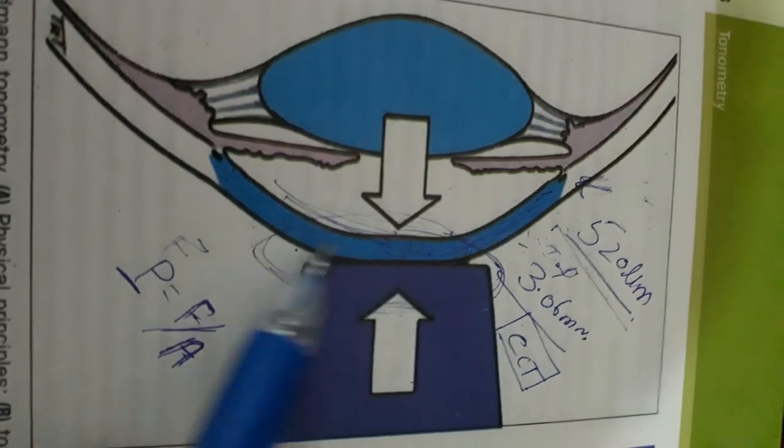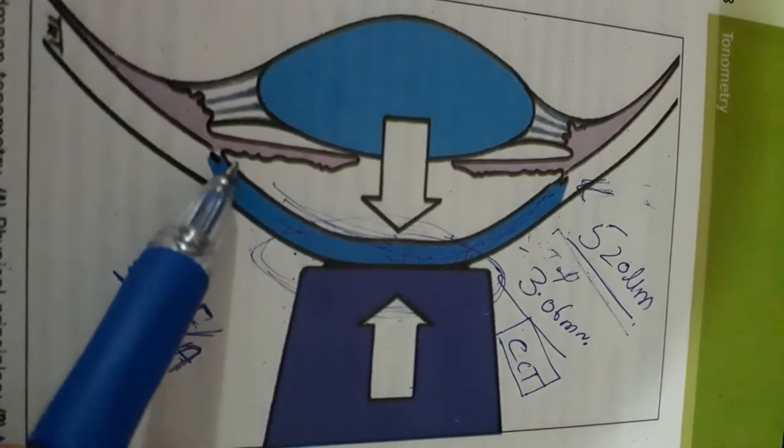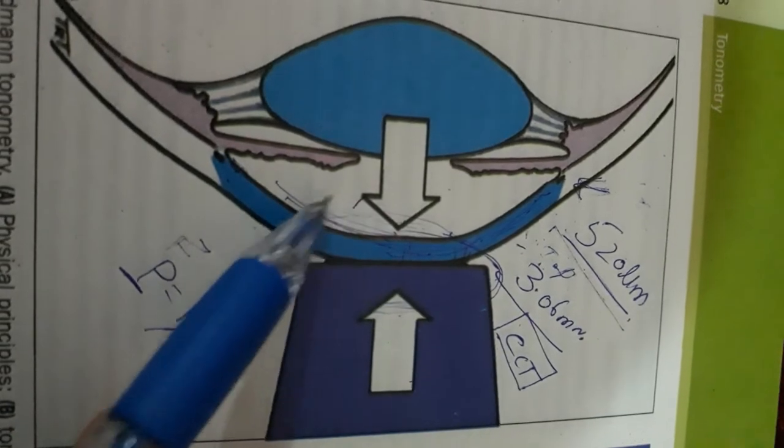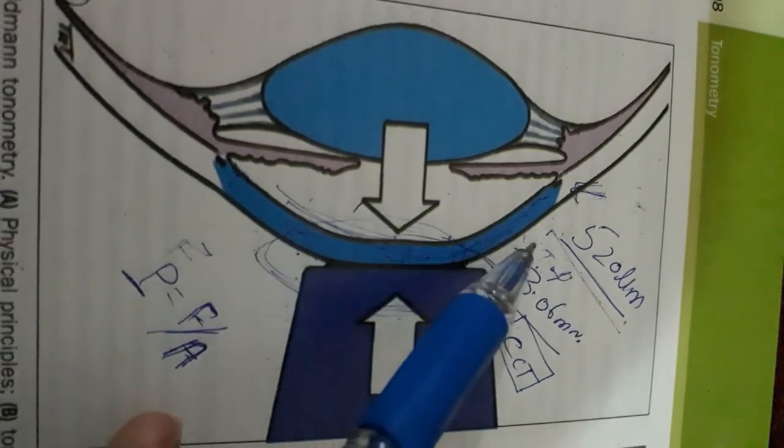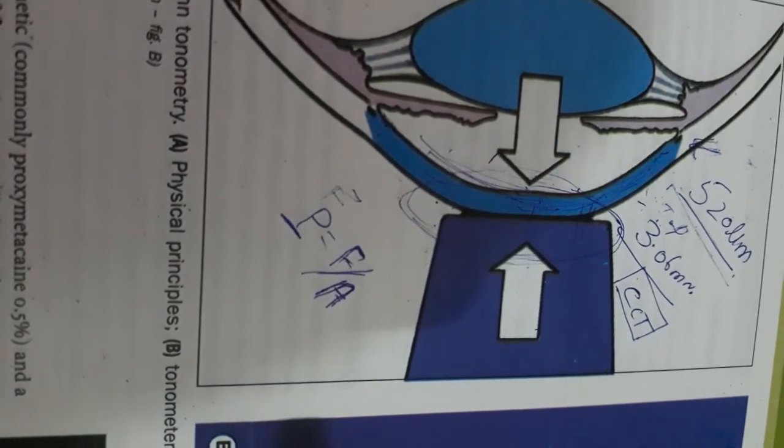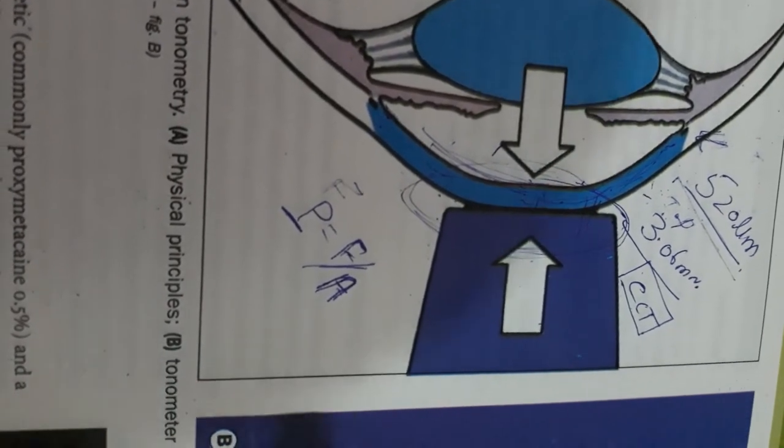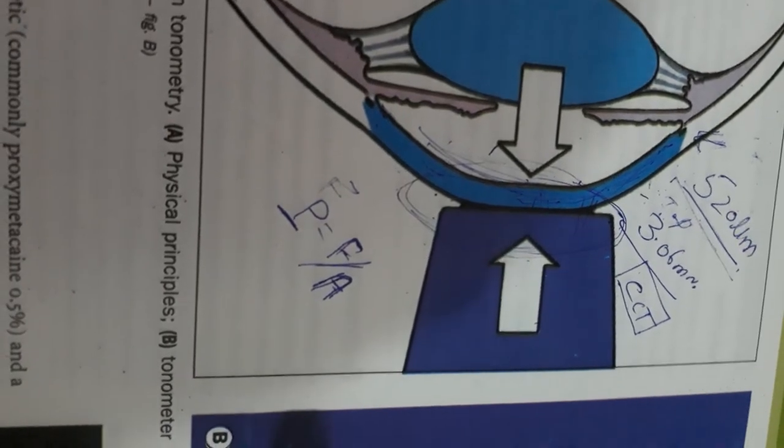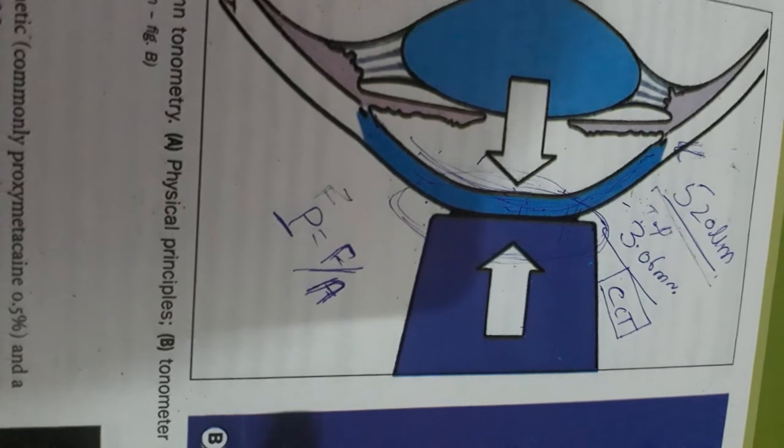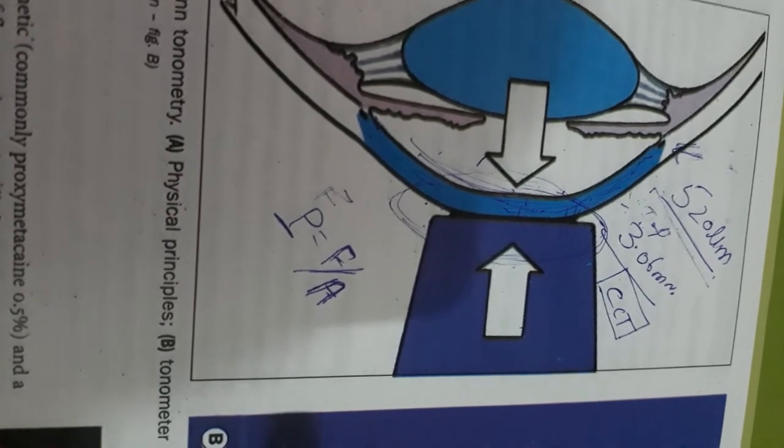In ocular hypertension, the cornea is thick and gives rise to false readings. In normal tension glaucoma, the cornea is thin. Other factors like corneal edema, astigmatism, and incorrect calibration can result in false readings, so manufacturer calibration is necessary prior to checking IOP.